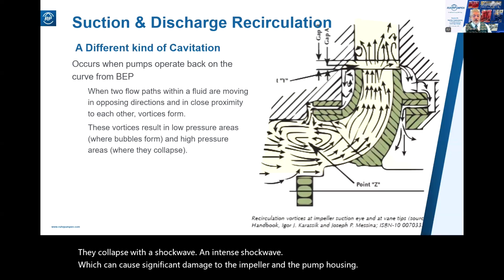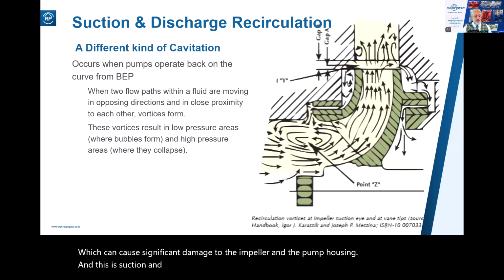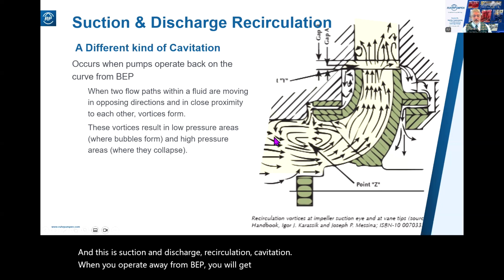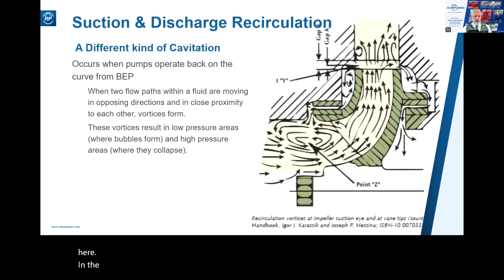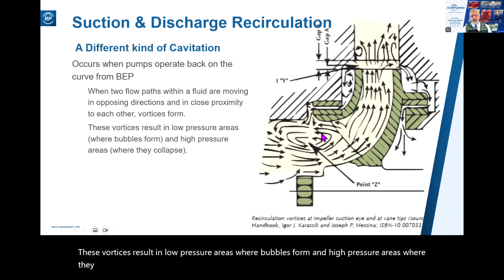And this is suction and discharge recirculation cavitation. When you operate away from BEP, you will get recirculation vortices here in the suction and here in the discharge. These vortices result in low pressure areas where bubbles form and high pressure areas where they collapse. They form here and they collapse here. Form, collapse.